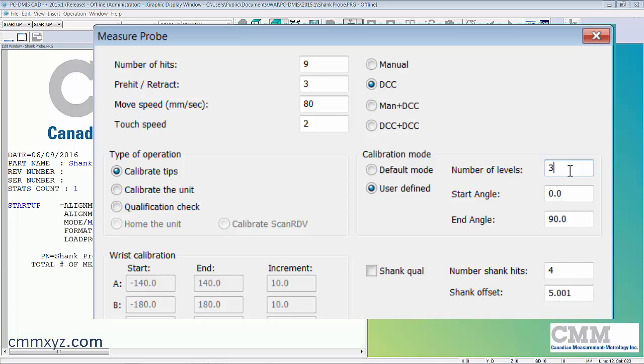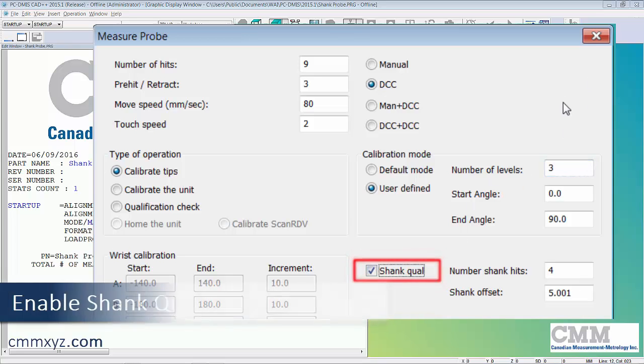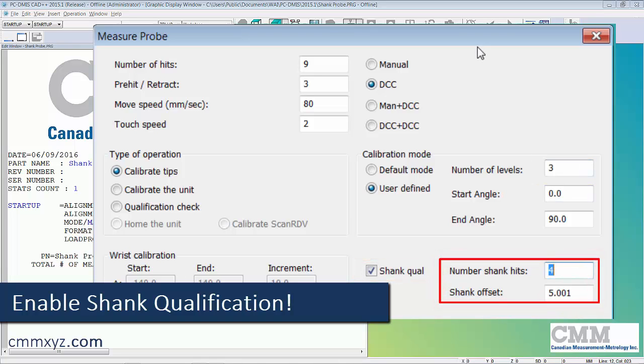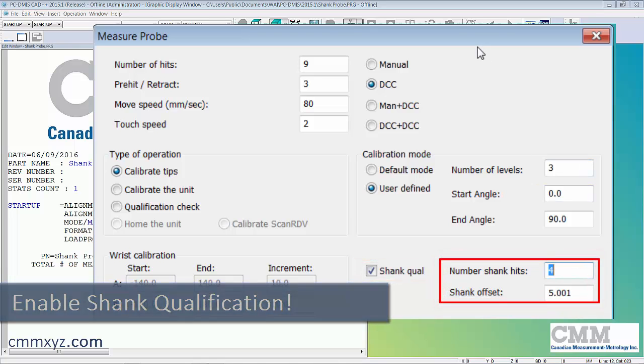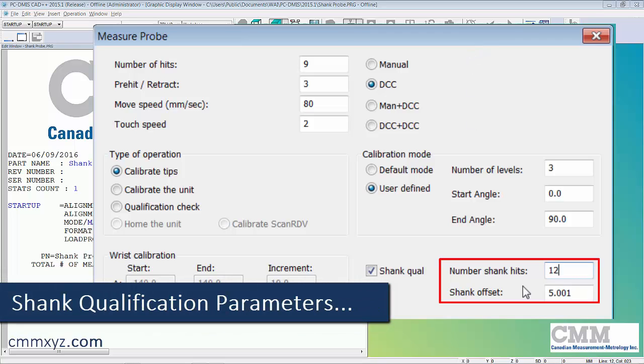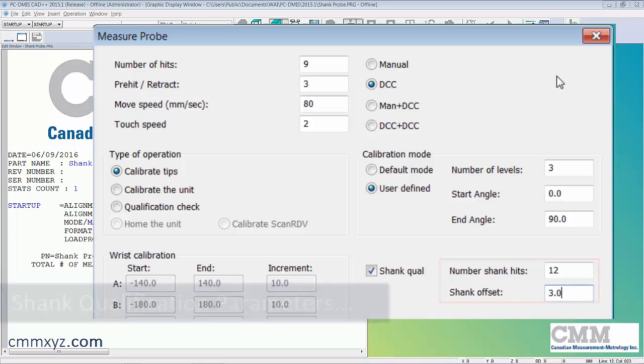What we're going to be doing with this tip is calibrating first as if it was just a regular ruby ball tip going through this calibration setting. But the special thing we do with the shank probe is we need to check the shank qualification box, specify the number of shank hits. I'll use 12.